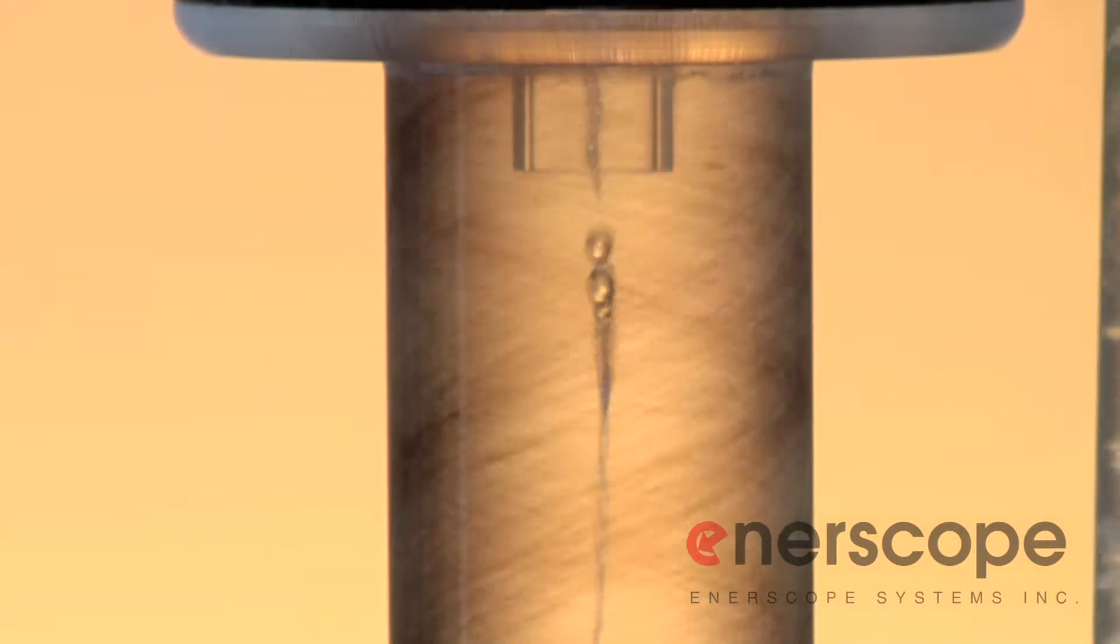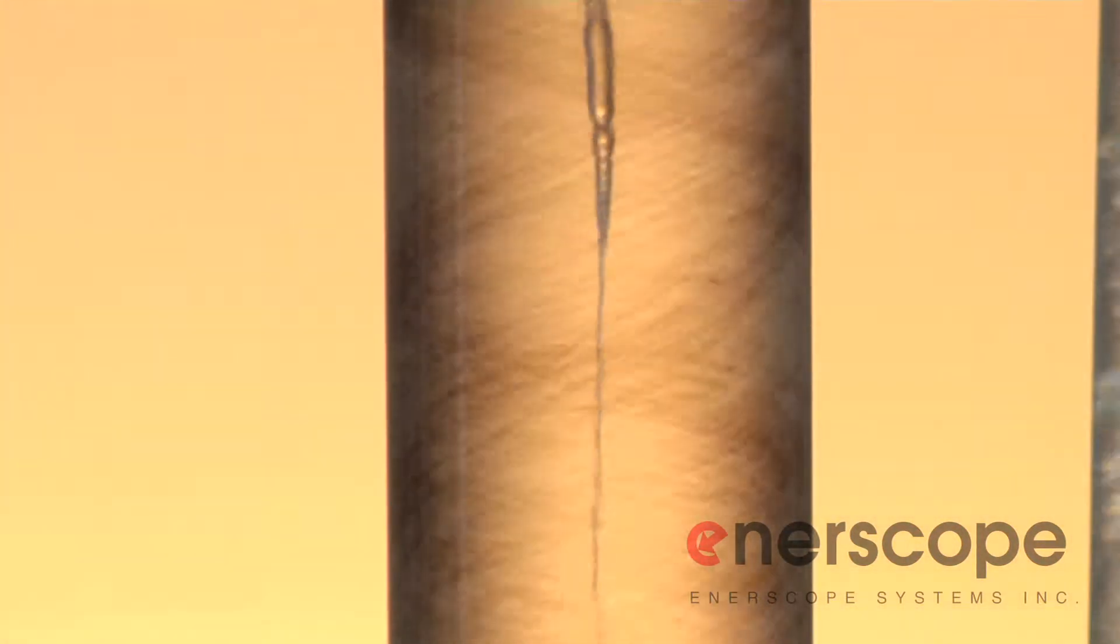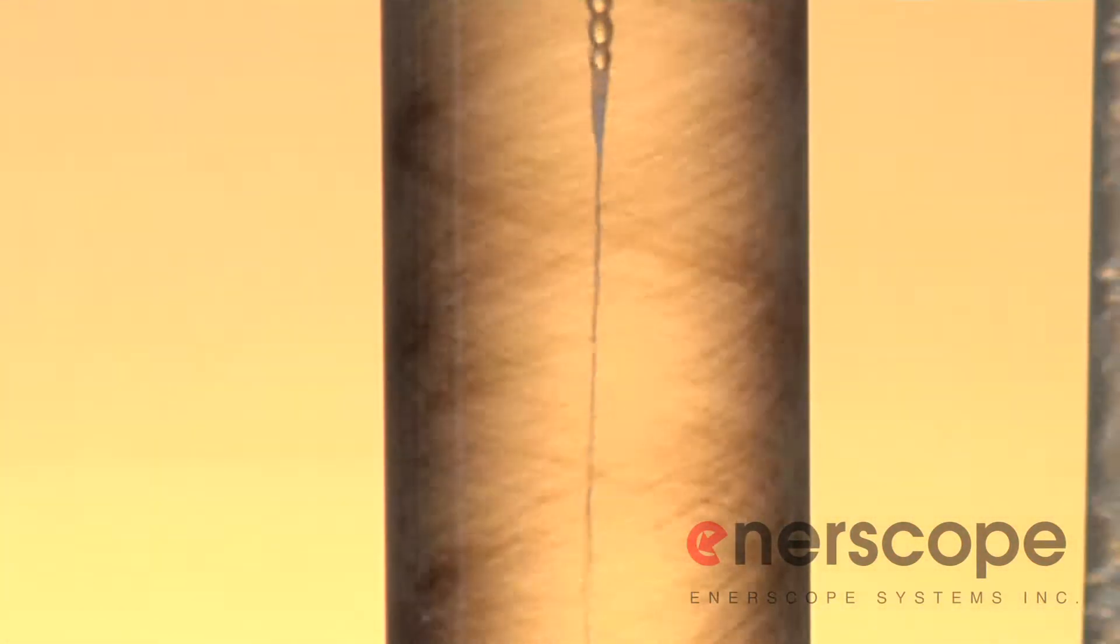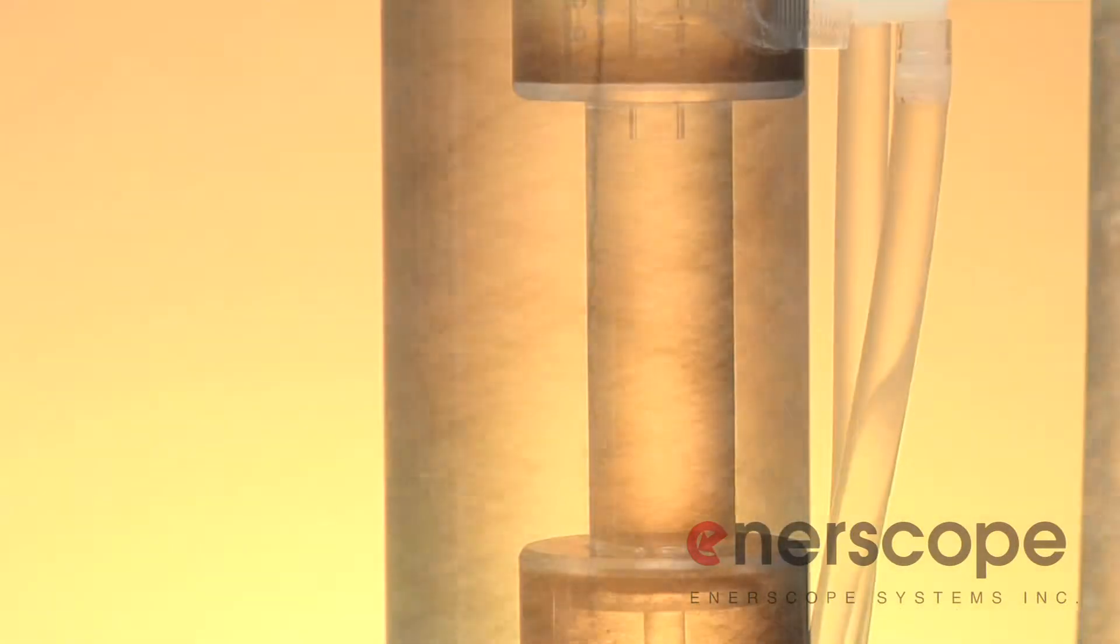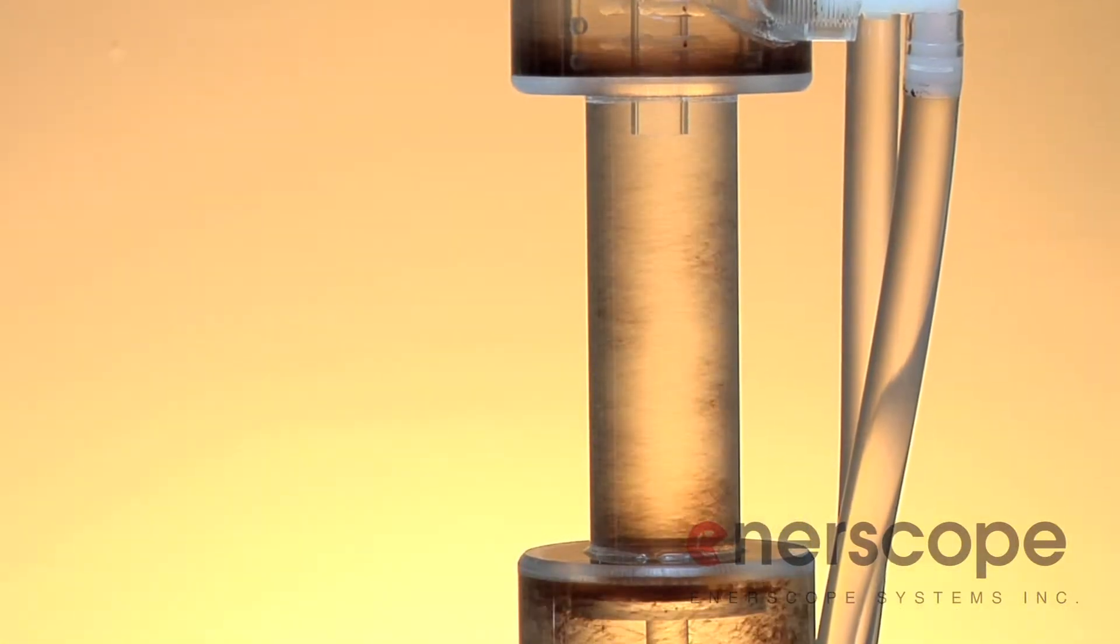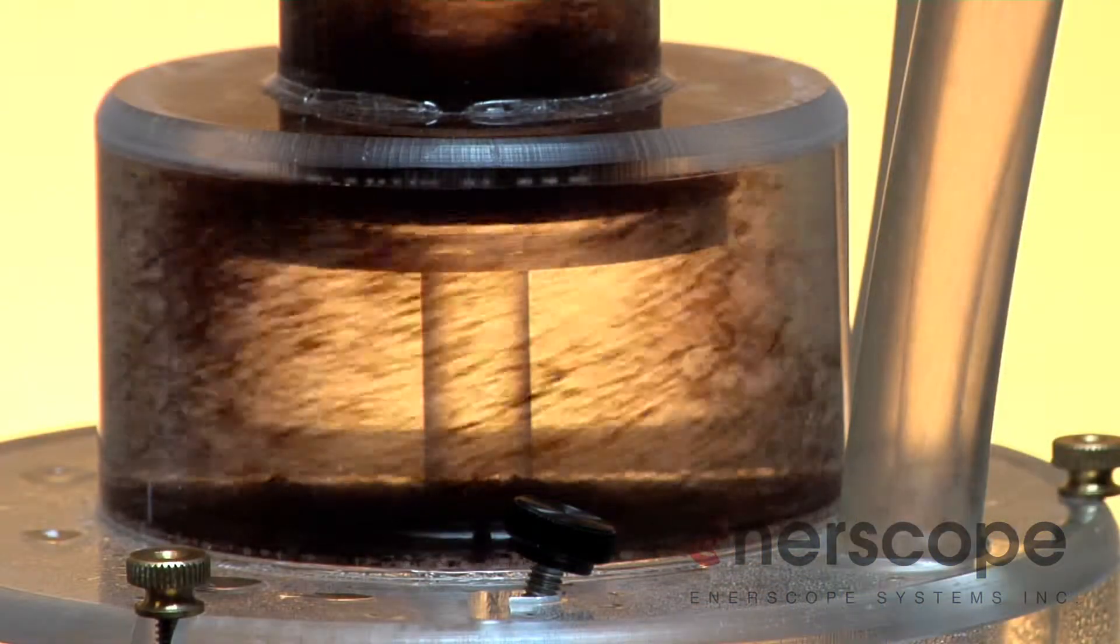The particles in the fluid are affected by the centrifugal action once in the separation chamber and make their way to the perimeter in a laminar flow before reducing their rotational velocity. The solids are drawn down and slowly settle into the solids collection chamber.